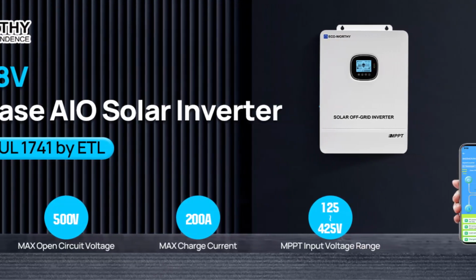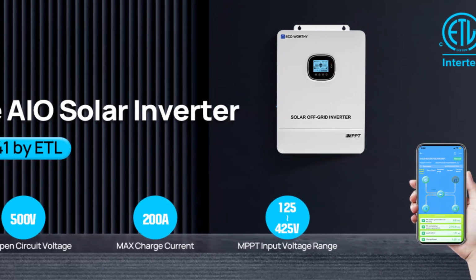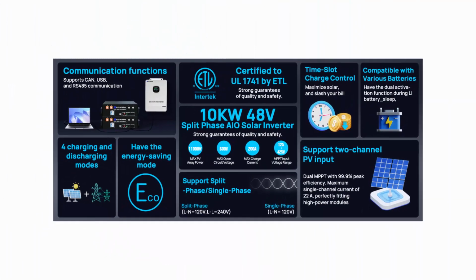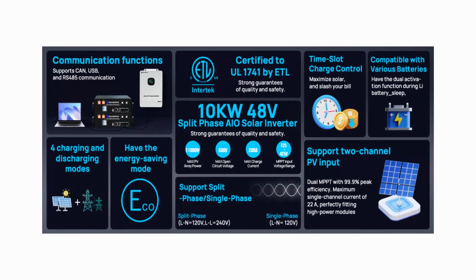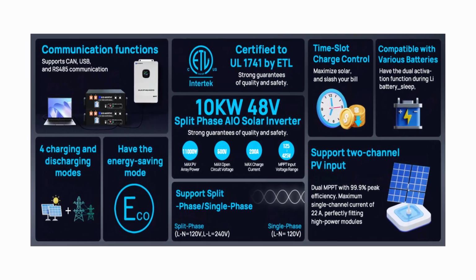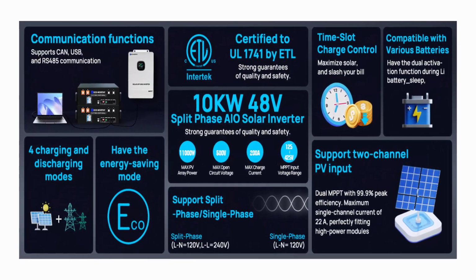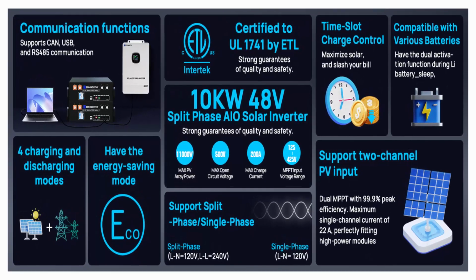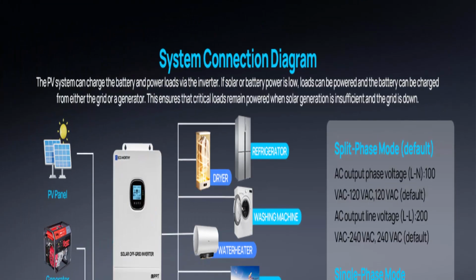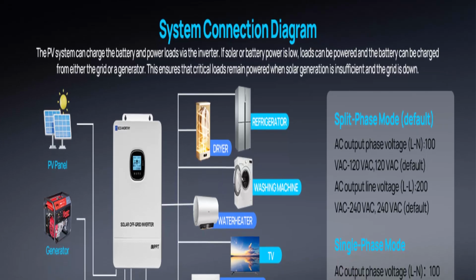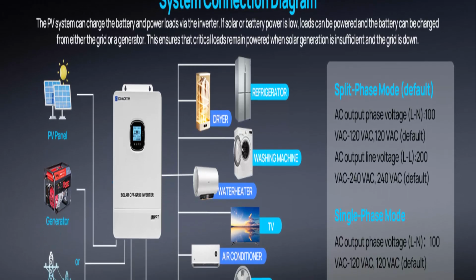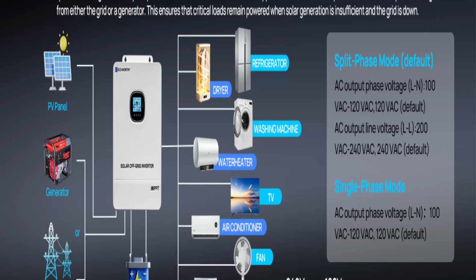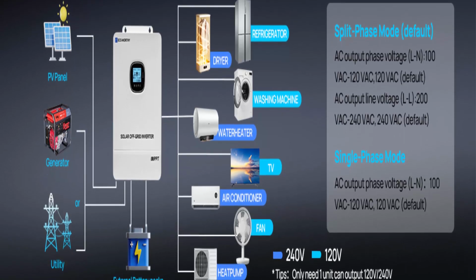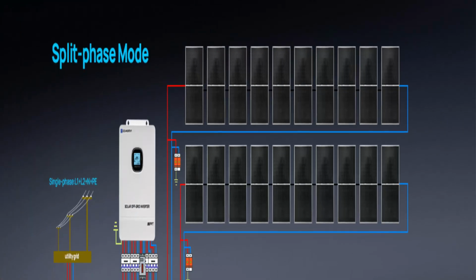Expandable system and battery compatibility, supports parallel connection of up to 6 units, 60 kW total output, for scalable power needs. Compatible with multiple 48 volt battery types, including AGM, gel, flooded, and lithium batteries. Communication ports include CAN, USB, and RS485 for seamless system integration.